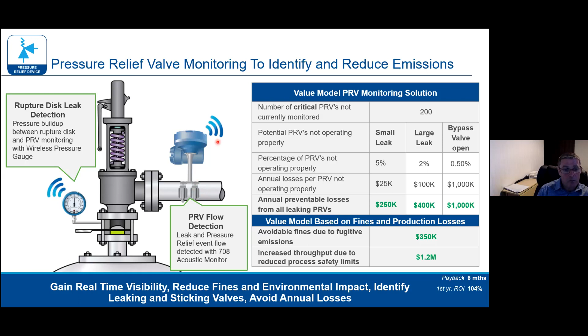Same device, different application: pressure relief valves. Like safety showers, there's a need to measure and record emissions to atmosphere of gases. There's two ways here - we can measure the ruptured disc using the wireless pressure gauge, and supplement this with the acoustic measurement, which listens for the line becoming active. When there's a release, the disc bursts, we hear the noise, see a change in temperature since it measures temperature as well, and we can measure the time and duration of any relief.